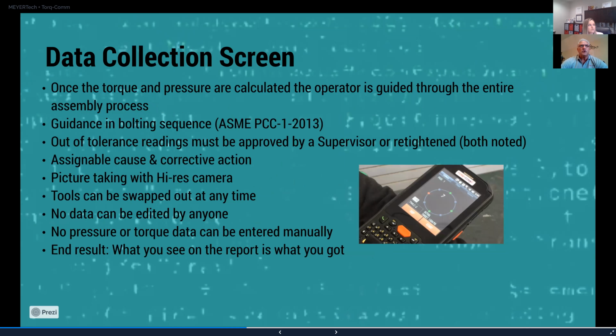Once the torque and pressure are calculated, the operator is guided through the entire assembly process, and that guidance is in accordance with PCC 1. Out-of-tolerance readings must be approved by a supervisor or retightened, and in either case both are noted. So if the pressure didn't get high enough on the hydraulic pump, and the torque wasn't high enough, it will alarm the operator and not allow him to continue until he either retightens it or calls a supervisor over, who then inputs his PIN code.